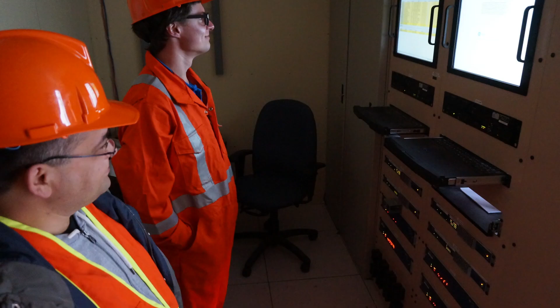For us, 61850 greatly reduces wiring in our substations, translating to reduced construction time and cost. It's about speed, allowing advanced protection that's better for customer reliability and reduces the chance of equipment damage, which is about cost savings. It lets us reconfigure protection systems much faster, increasing reliability and reducing troubleshooting. Because of all this, we see reduced commissioning time, positioning SaskPower better for the future.